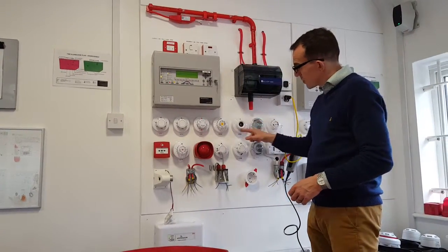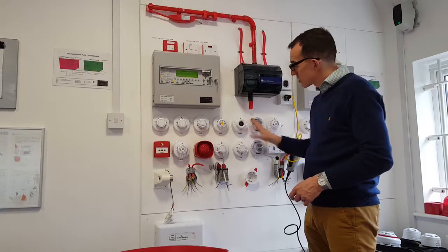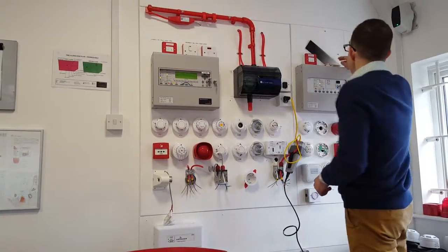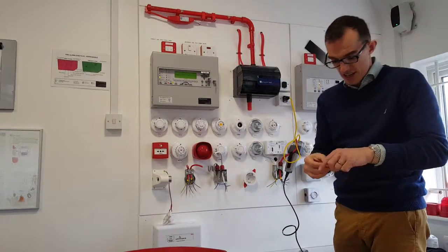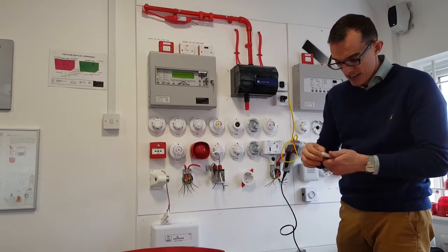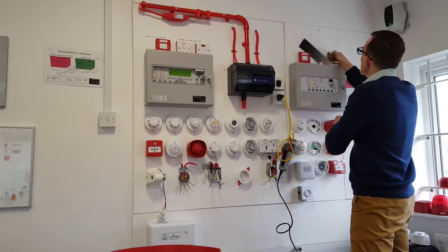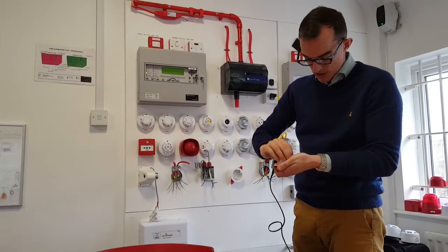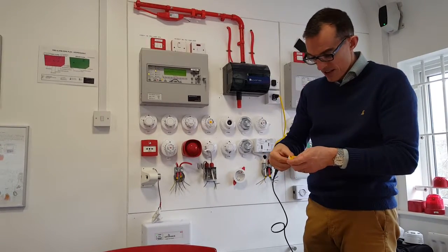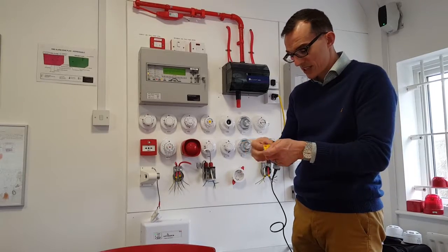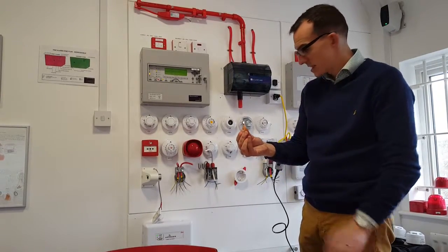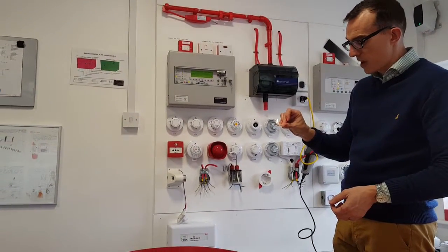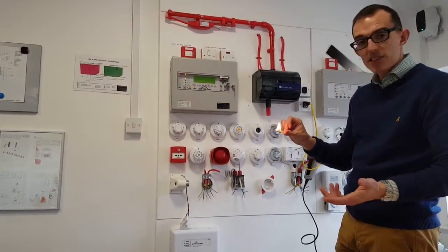So this is a flame detector. This one here. It doesn't work if you set it off with smoke or with heat, or if you cover it up. But if I was to get a match and set the match on fire, on that one, on these ones, if we get a match and we light it, now there won't be a lot of smoke that comes out of this, but the unique signature in a flame, which is ultraviolet and infrared, sets off the alarm.